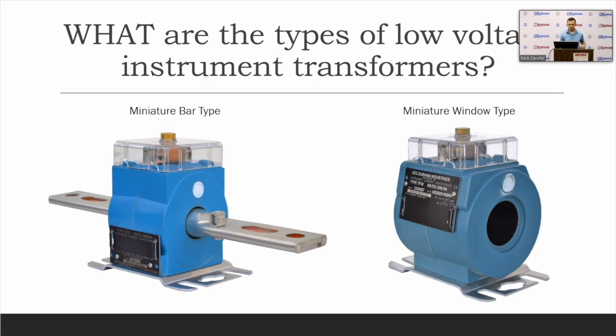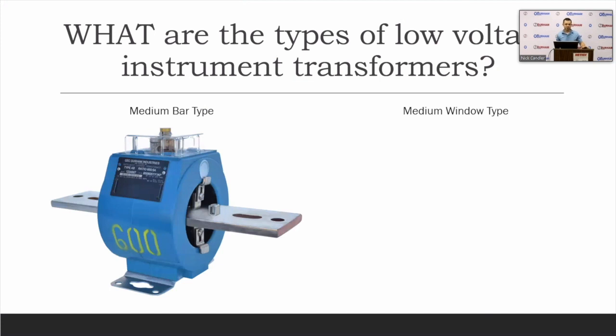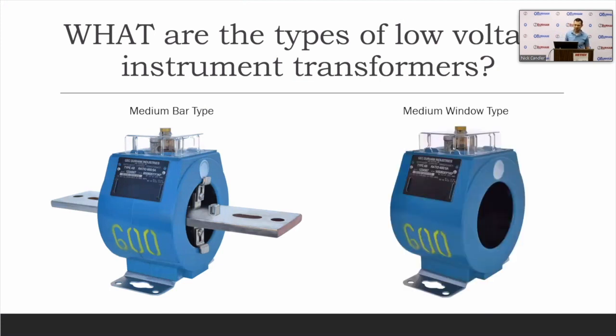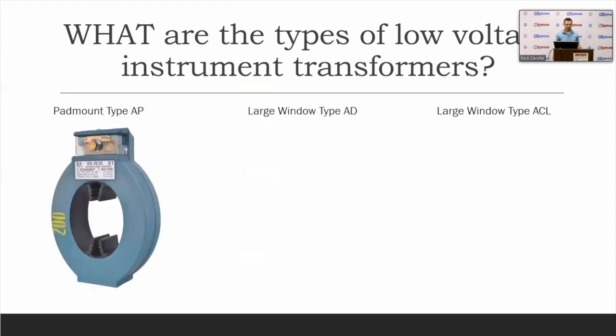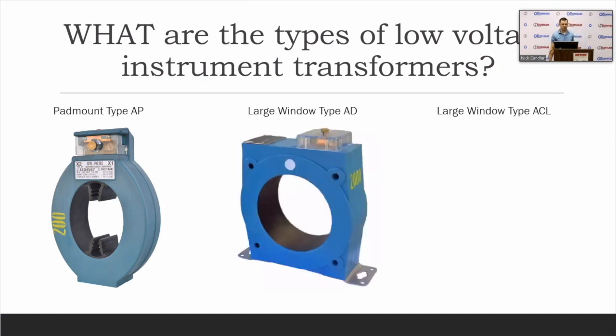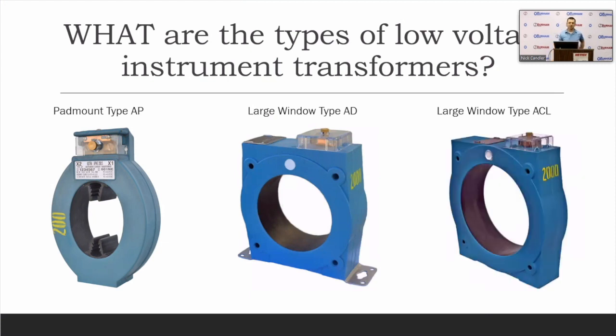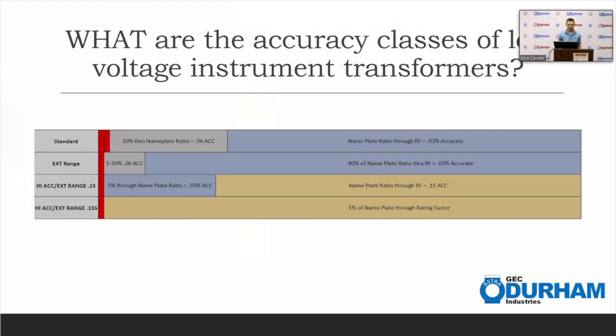You've seen a lot of these before, I'm sure. You've done many installations. There's a medium bar type transformer, and then there's also a medium window type transformer. The context and the application is what's really driving this. So there's a Padmount AP style of transformer. These are your large oval transformers that will go on those Padmount spades, Padmount transformers, or these will also go around your busing in a secondary connection cabinet. So we'll see one of those later. Large window type ADs and your large window type ACLs. These are the 5 prominent types of instrument transformers that your utilities are going to make use of.